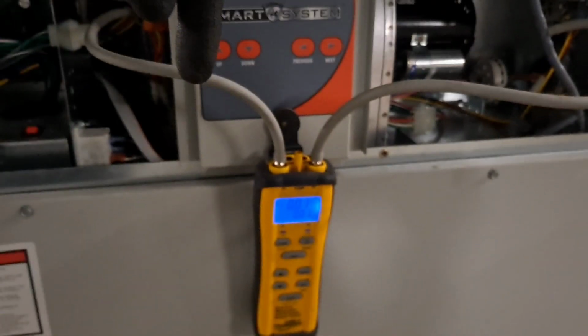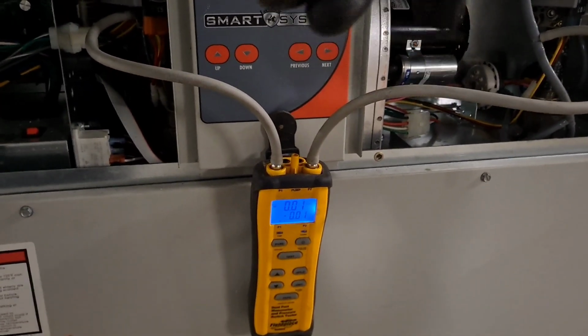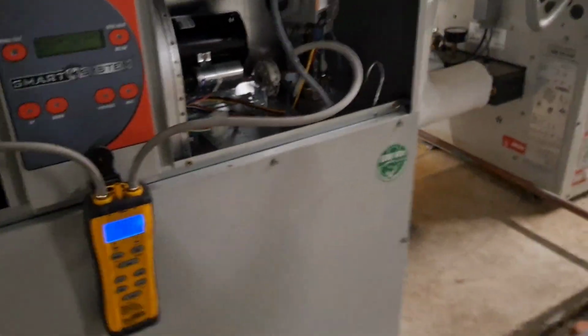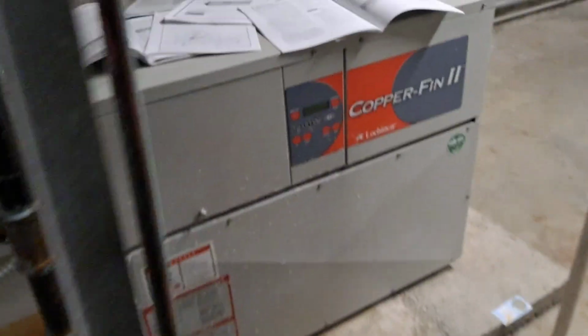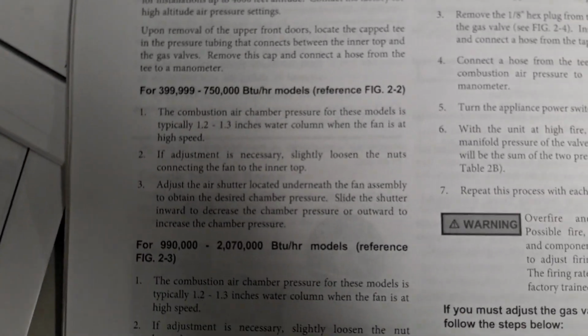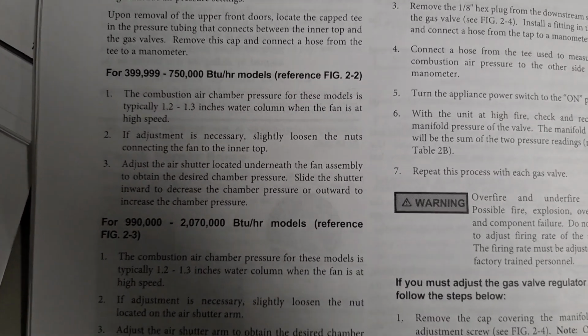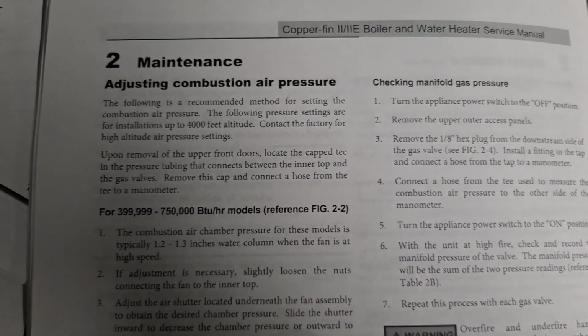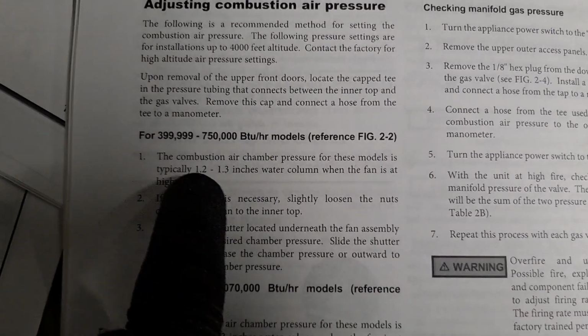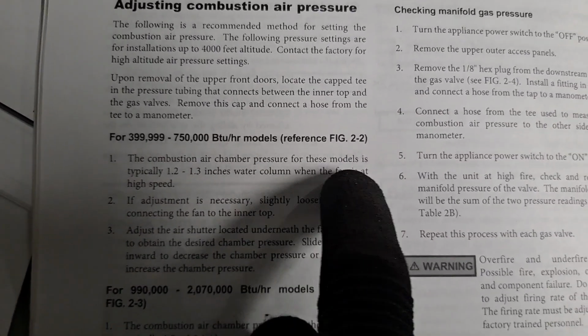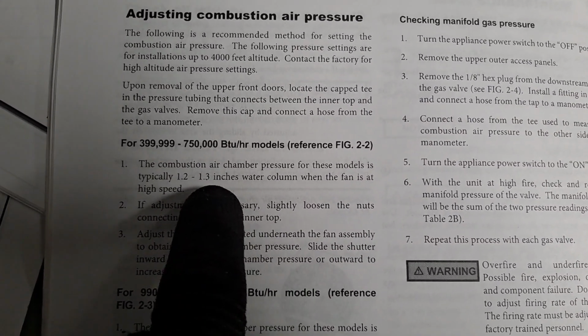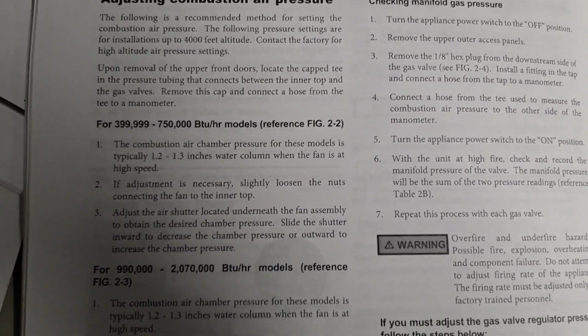Now that's not 1.8 inches here. That's 1.8 inches differential here, here. Also is in the manual, which is pretty good. This is the service manual. They also give you your inches water column reading for your combustion air. So this is adjusting combustion air pressure, and you can see right here the combustion air chamber pressure for these models is typically 1.2 to 1.3 inches water column when the fan is running at high speed.